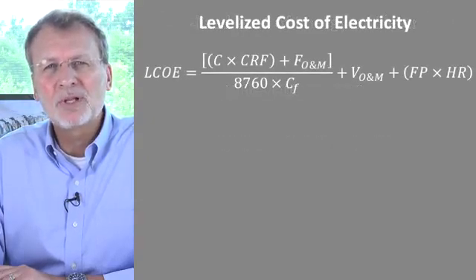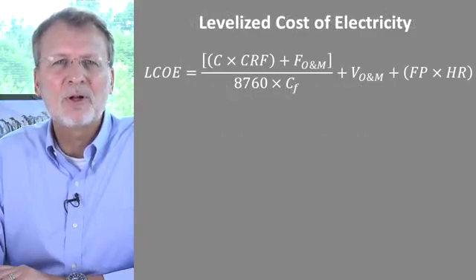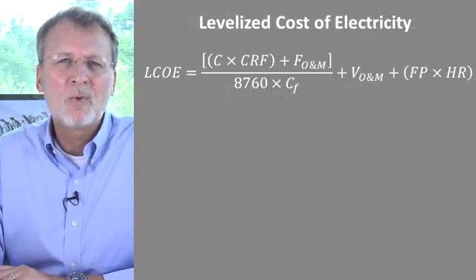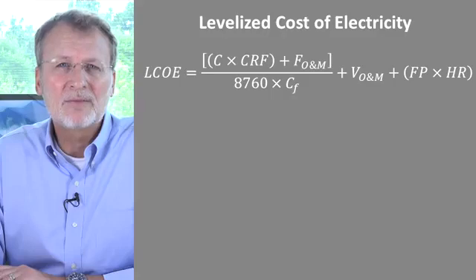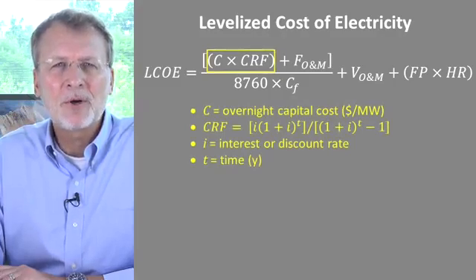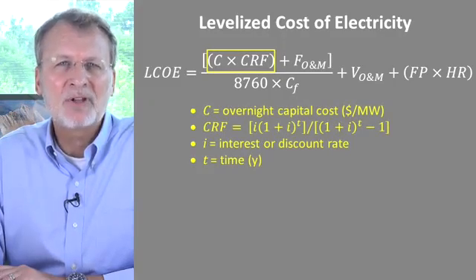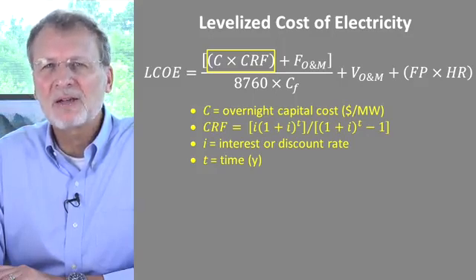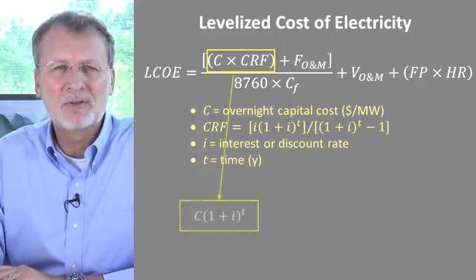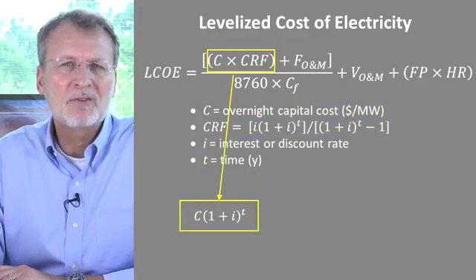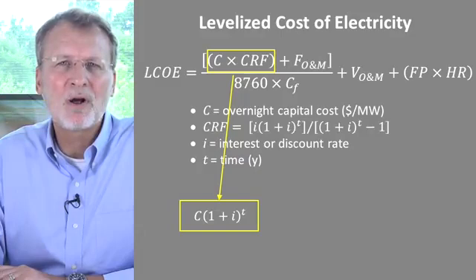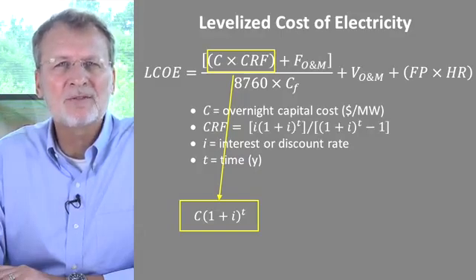The LCOE for a plant is calculated using the following equation. While the equation may look a little confusing, it's best understood if broken down into its component parts. The first component is the capital cost of the plant amortized over the lifetime of the plant. This component is in fact made up of two sub-components. The first sub-component expresses the purchase price of the plant in terms of what the plant would cost if bought new a plant lifetime from now.